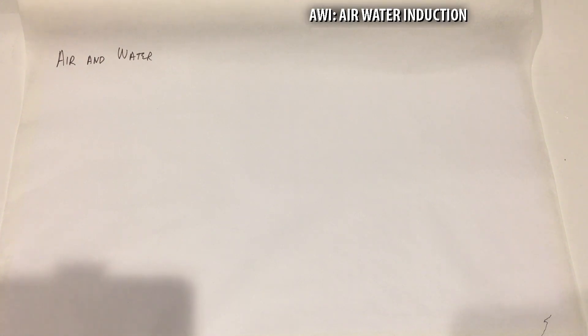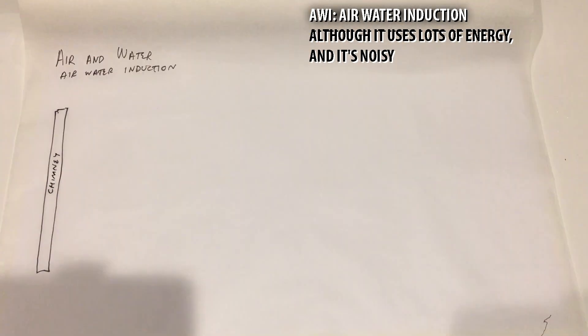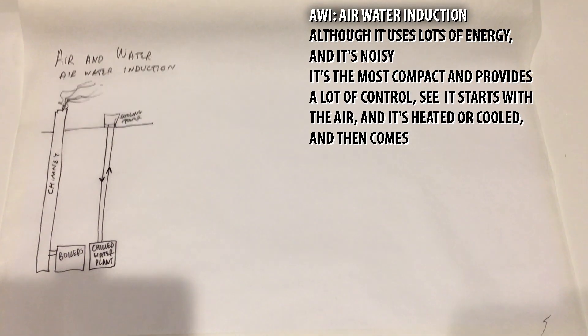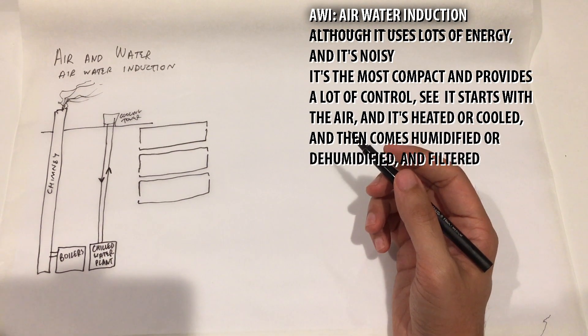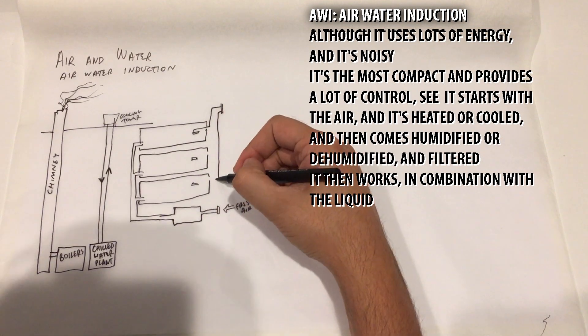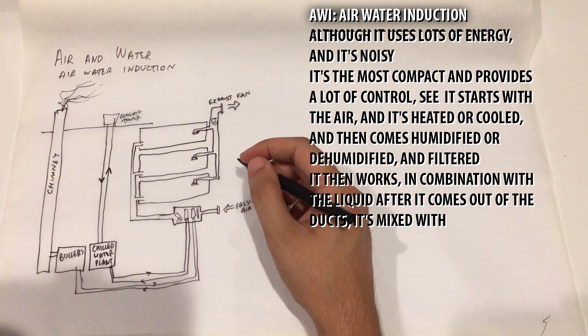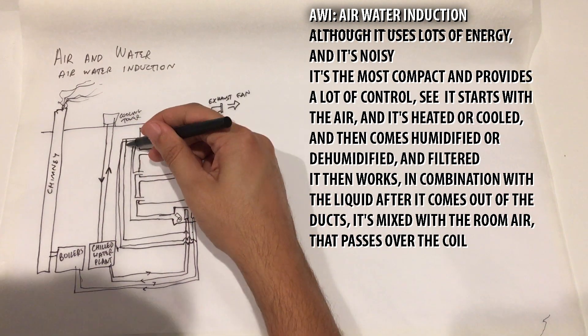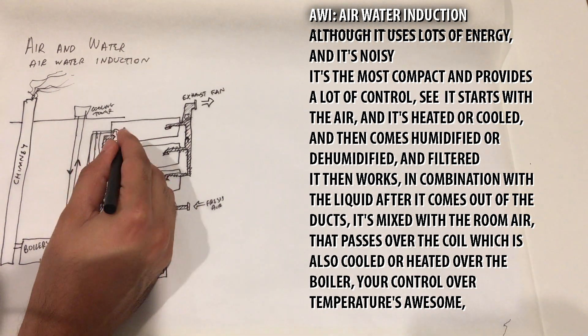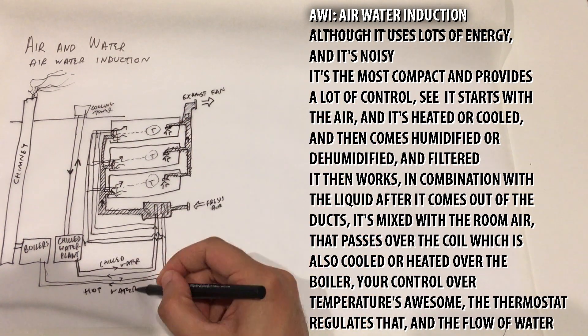The final type combines air and water — it's the hybrid system AWI, Air-Water Induction. It requires the least space of all systems. Although it uses lots of energy and is noisy, it is the most compact and provides a lot of control. Air is heated or cooled, then humidified or dehumidified. After coming out of the ducts, it's mixed with room air that passes over a coil, which is also cooled or heated. The thermostat regulates the flow of water for awesome temperature control.